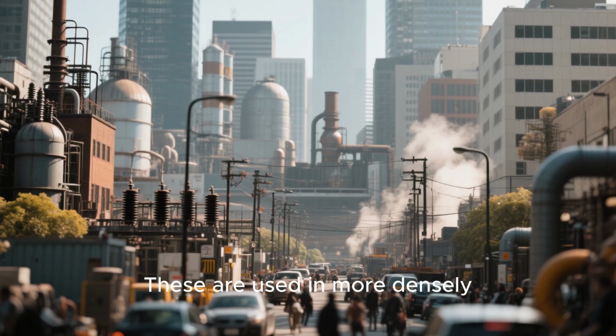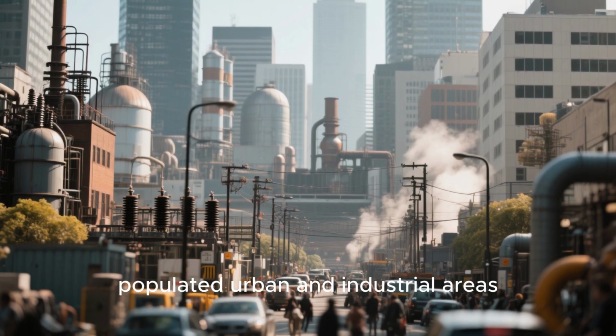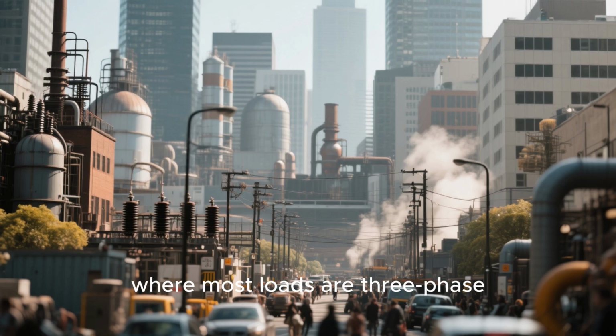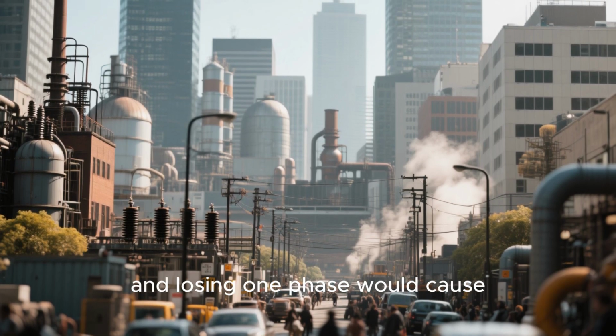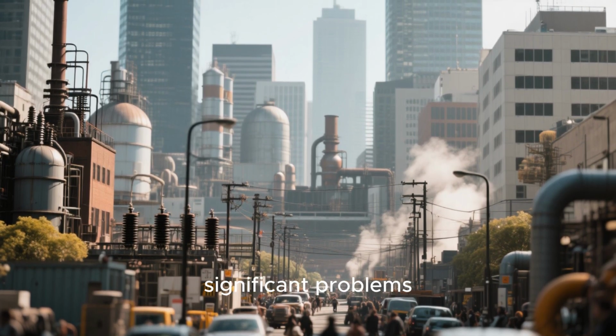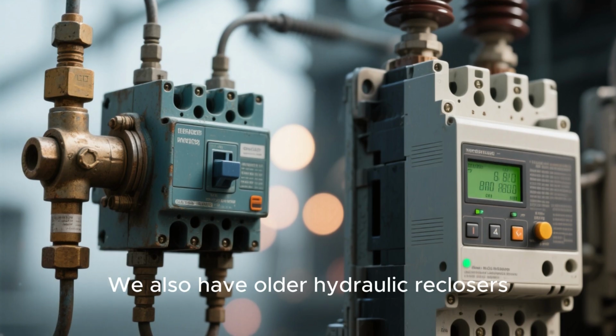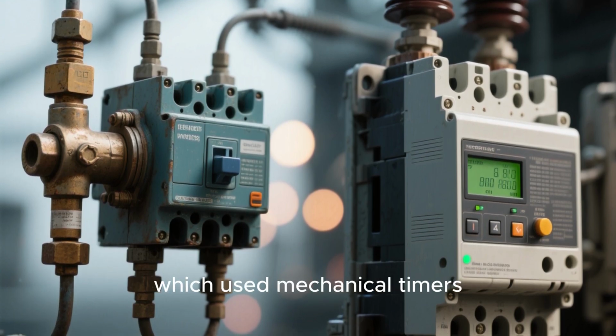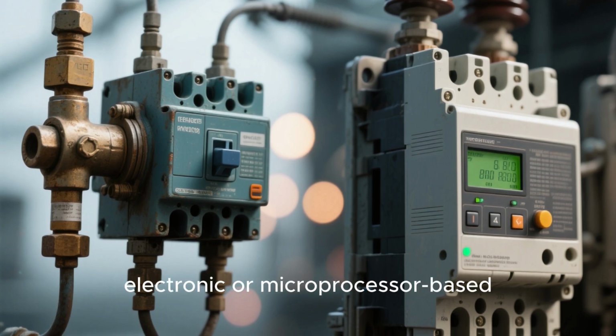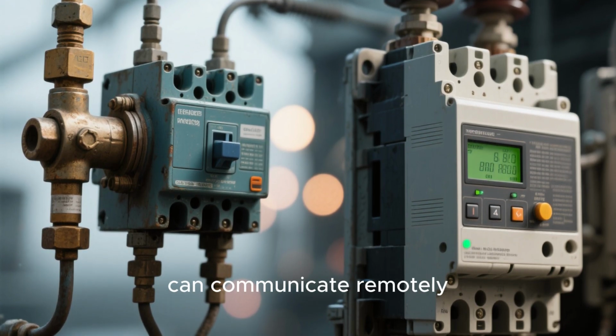These are used in more densely populated urban and industrial areas where most loads are 3-phase, and losing one phase would cause significant problems. We also have older hydraulic reclosers, which use mechanical timers and were less flexible, versus modern electronic or microprocessor-based reclosers, which are fully programmable, can communicate remotely, and are the standard today.